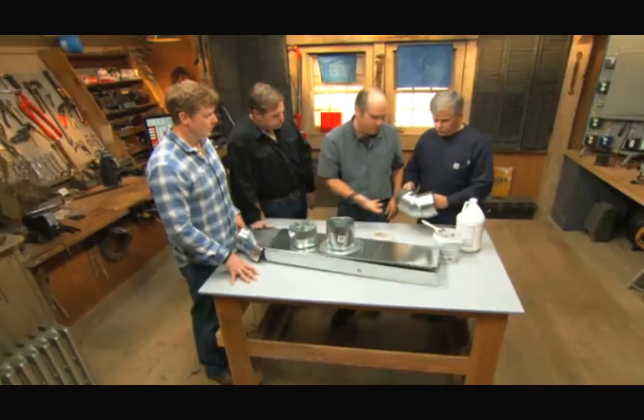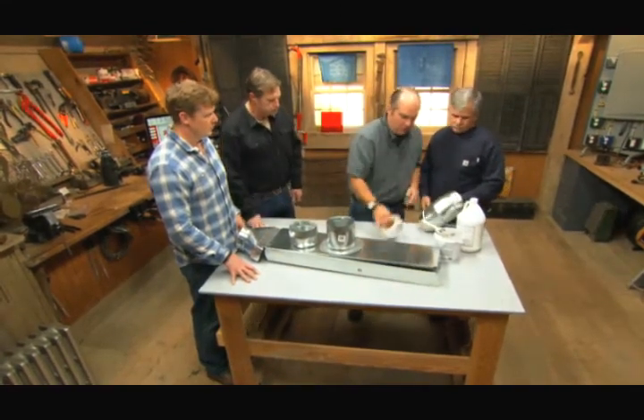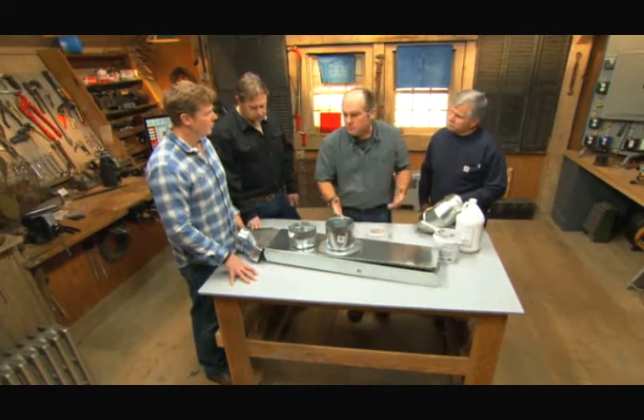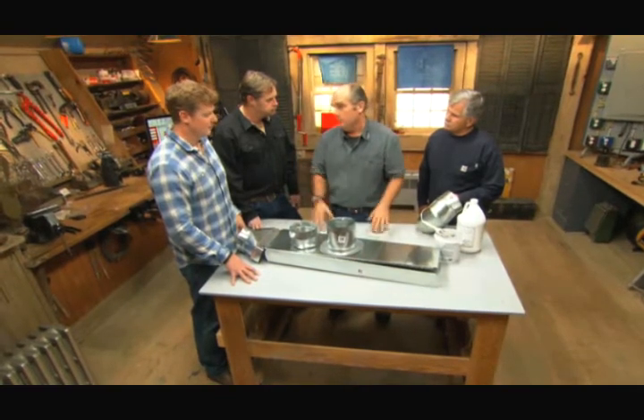What about all these swiveled elbows? Yeah, the swivels are never airtight, so you're going to have to use a mastic or the foil tape right here. The issue is we're losing 20, 30, 40% of the air that should be going into the living space for heating and cooling going to the wrong place. Wow. But you're not really losing it. It's staying in the house.